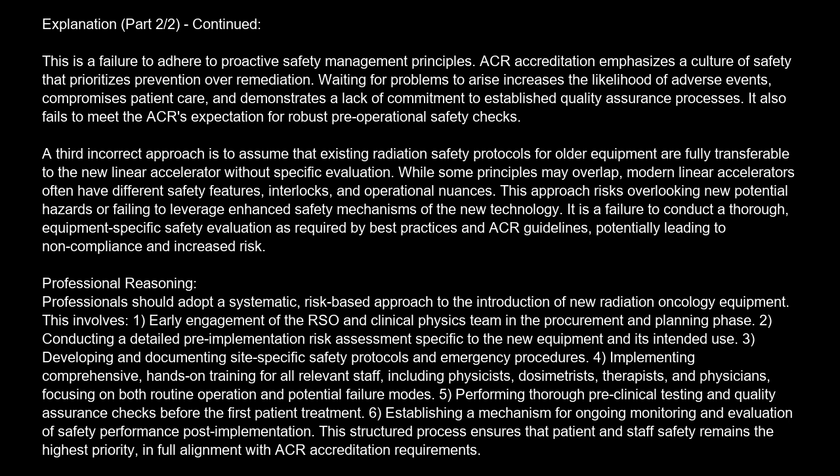It also fails to meet the ACR's expectation for robust preoperational safety checks. A third incorrect approach is to assume that existing radiation safety protocols for older equipment are fully transferable to the new linear accelerator without specific evaluation. While some principles may overlap, modern linear accelerators often have different safety features, interlocks, and operational nuances. This approach risks overlooking new potential hazards or failing to leverage enhanced safety mechanisms of the new technology.